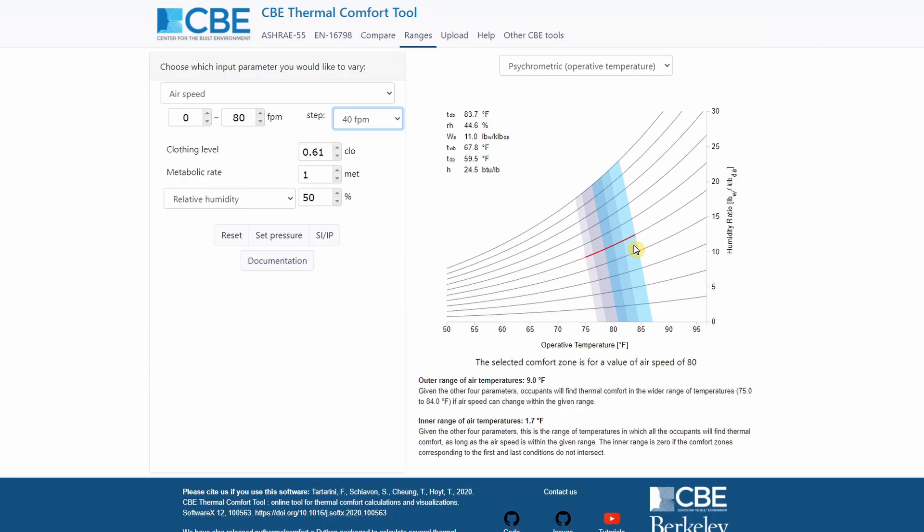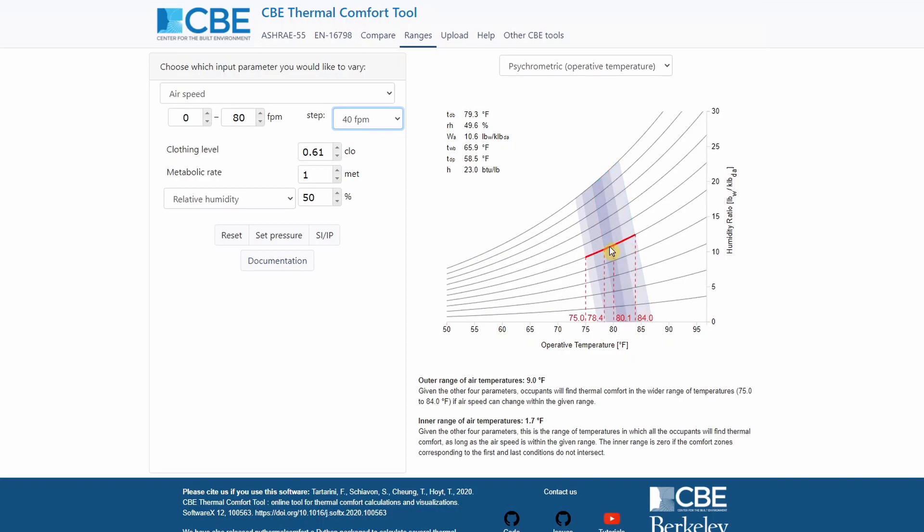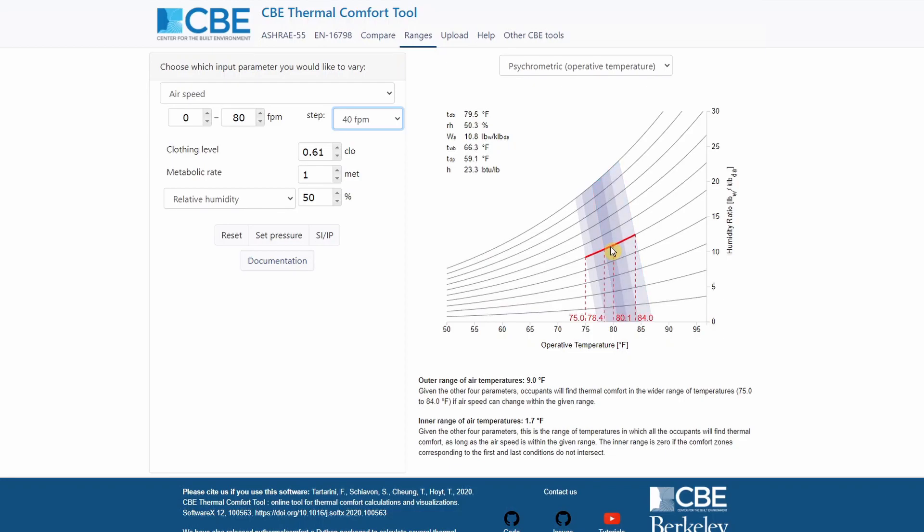One which is the comfort region for an airspeed of 80 feet per minute, then we have one which is 40, and one which is zero feet per minute. You can see that where the region overlaps, it means that people exposed to all these conditions are both going to be comfortable, but also shows us the outer region. If people have control and can select their fan speed based on their preference, we can actually see that people are going to be comfortable between 75 Fahrenheit up to 84 Fahrenheit.